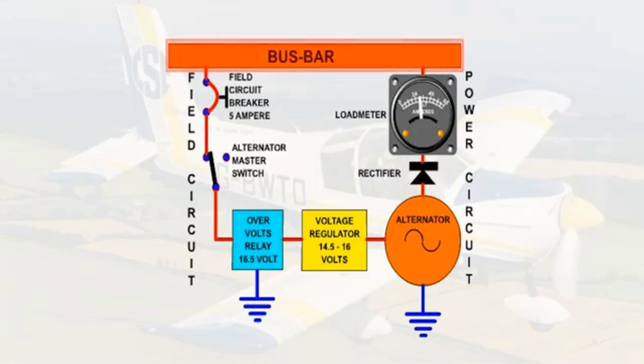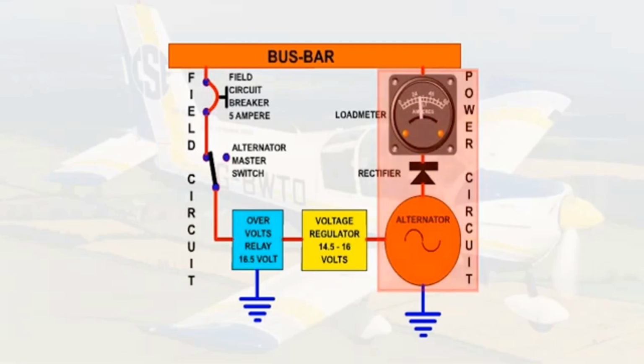At the top of the diagram you can see the bus bar, which we previously said was a distribution point for the output of the alternator or generator. To the left is the field circuit, and to the right is the power circuit. The field circuit carries a relatively small current. The current flows through the field windings and is used to generate a magnetic field inside which the armature of the alternator rotates.